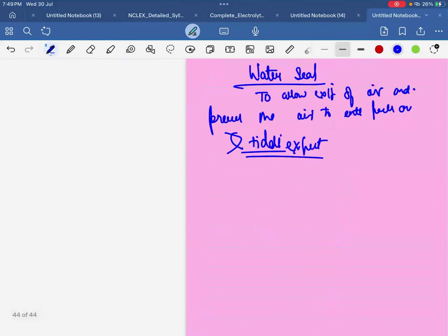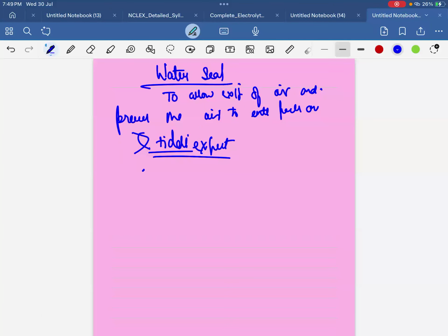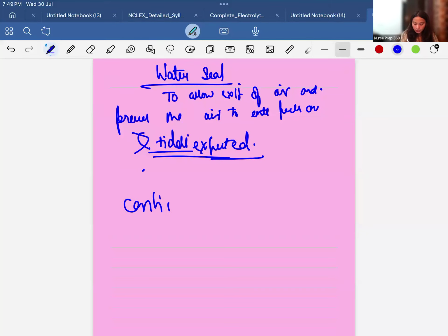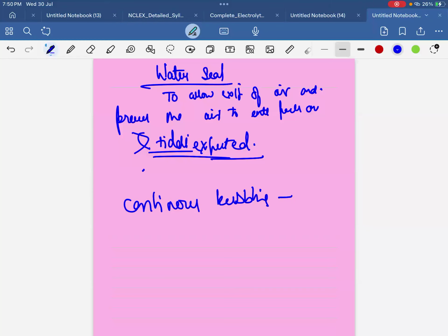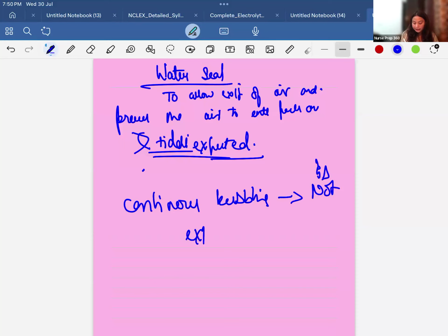Okay. Now write it down. Tidaling is expected. Continuous bubbling is not expected at all. Understood?